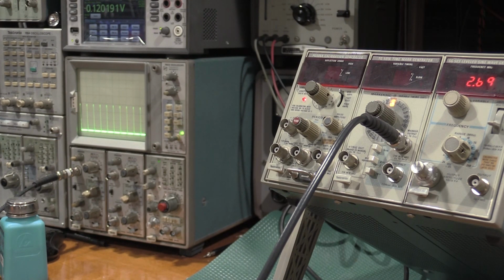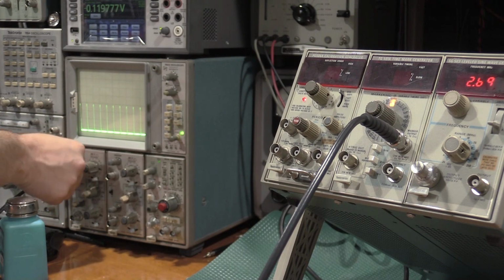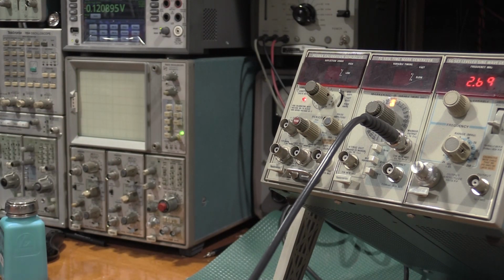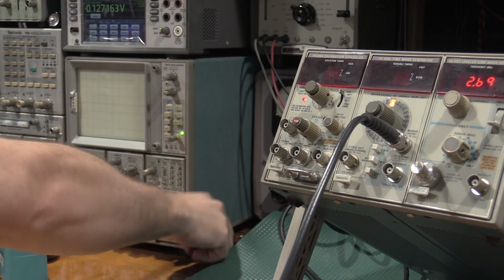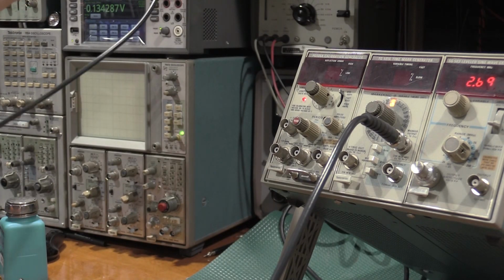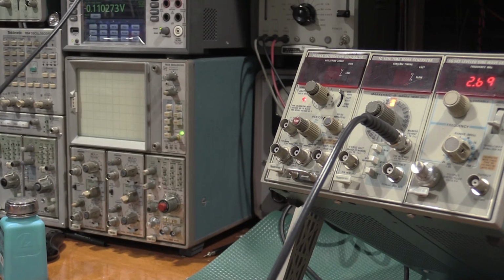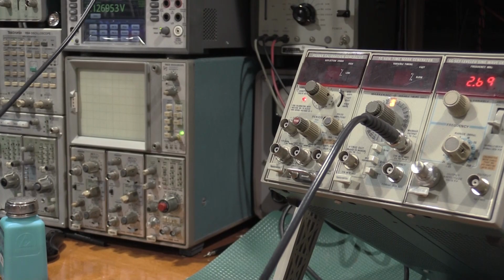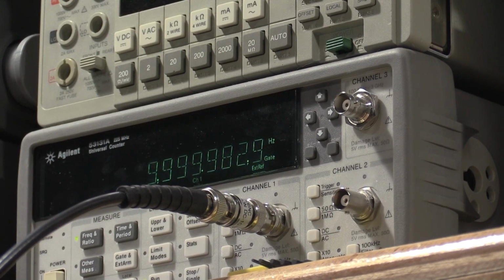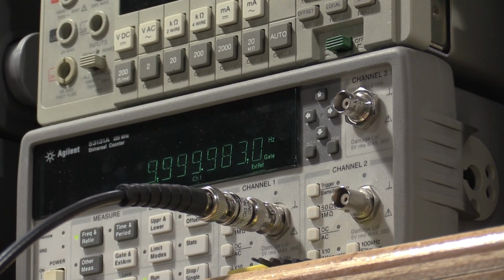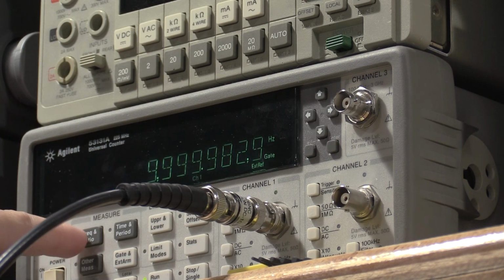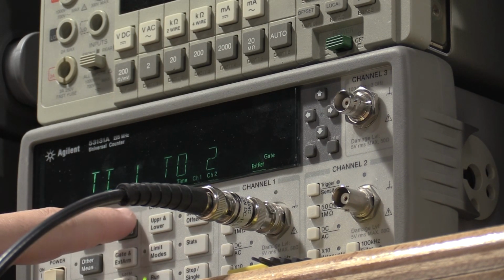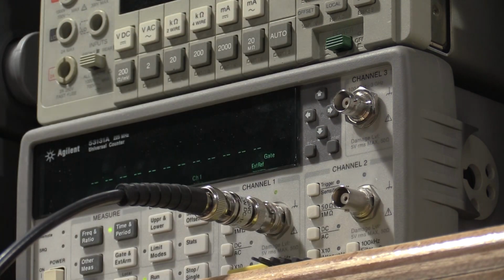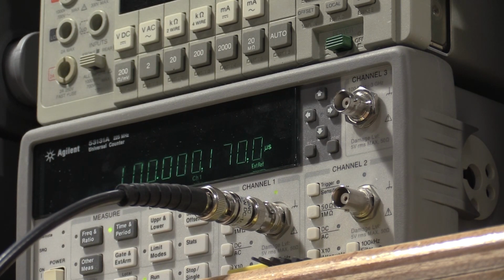Since we're here, we're just spot checking stuff. I am going to do a full calibration on these for their owner. Wow, but that is really close. And that's with the frequency counter not warmed up. I just turned it on. So we'll go to time and period 1. And my period is 100 microseconds, 0.1 millisecond.